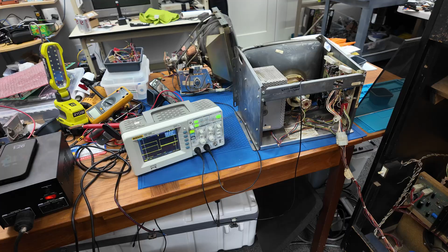Since we're dealing with a brightness problem, one thing we should check is the Z signal coming into the deflection board. The board has X, Y, and Z inputs, and the X and Y control the position of the vector beam on the screen, and the Z is the intensity. So the Z should be between 0 and 4 volts. 0 volts is the lowest intensity, and 4 volts is maximum intensity.